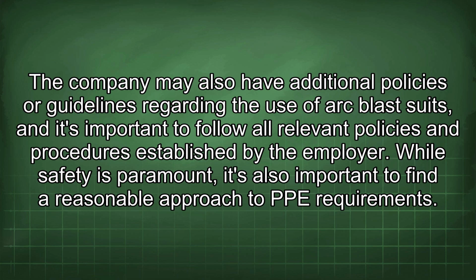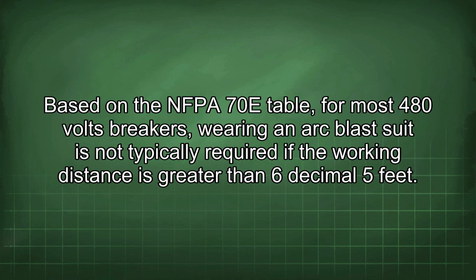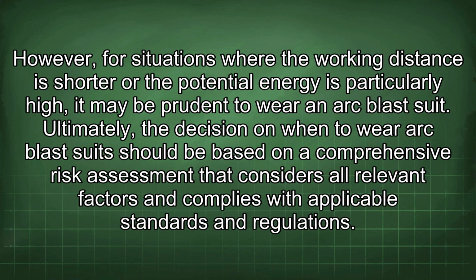While safety is paramount, it's also important to find a reasonable approach to PPE requirements. Based on the NFPA 70E table, for most 480 volts breakers, wearing an arc blast suit is not typically required if the working distance is greater than 6.5 feet. However, for situations where the working distance is shorter or the potential energy is particularly high, it may be prudent to wear an arc blast suit. Ultimately, the decision on when to wear an arc blast suit should be based on a comprehensive risk assessment that considers all relevant factors and complies with applicable standards and regulations.